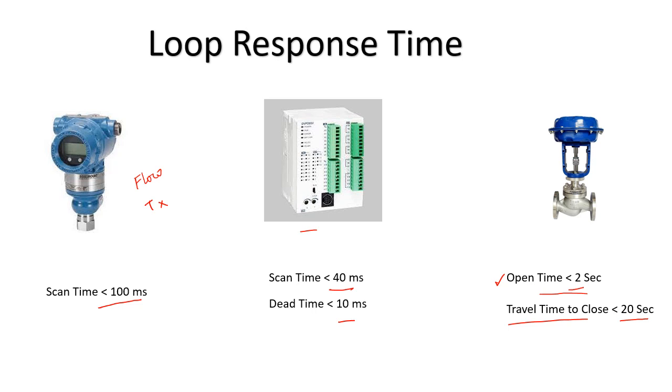Another thing to notice in this portion is the scan time of the control system. This is not an emergency shutdown system or a safety system. Rather, it is a control system. So one may argue, as all control systems are in the distributed control system, what is the problem of having the anti-surge control system also in the DCS? The main problem here is related to the scan time.